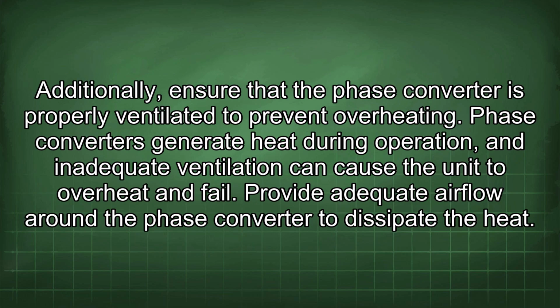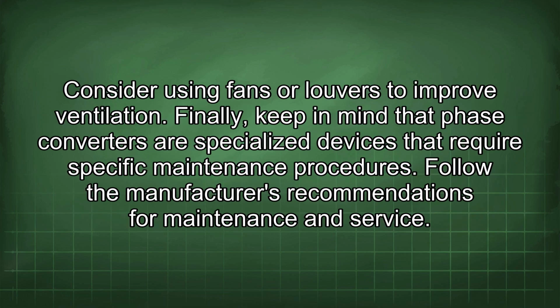Additionally, ensure that the phase converter is properly ventilated to prevent overheating. Phase converters generate heat during operation, and inadequate ventilation can cause the unit to overheat and fail. Provide adequate airflow around the phase converter to dissipate the heat. Consider using fans or louvers to improve ventilation.